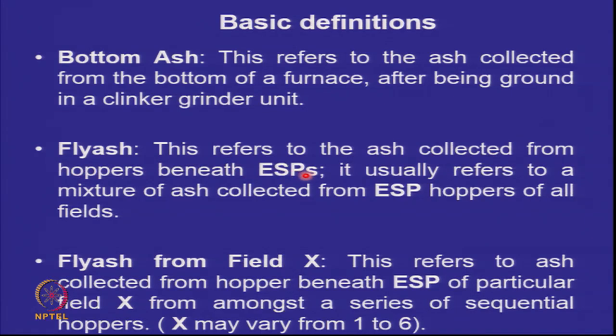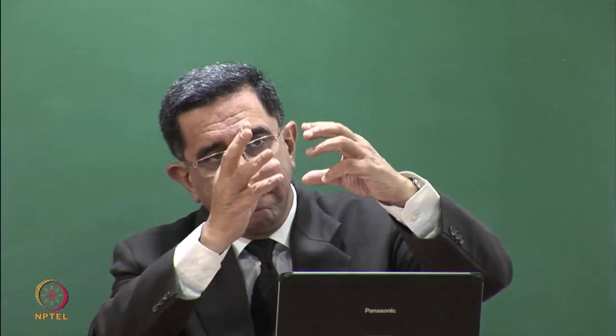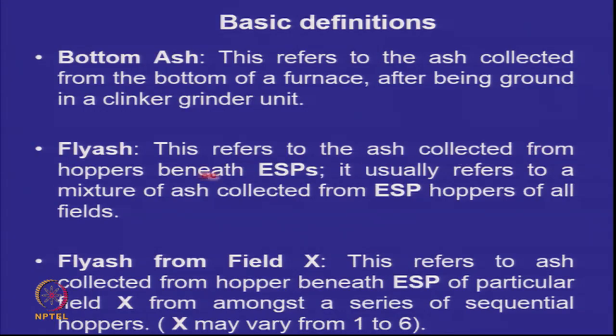Fly ash refers to the ash collected from the hoppers beneath the electrostatic precipitators (ESPs). As flue gases pass through a series of plates — referred to as fields (1 through 6) — particles settle progressively: coarser particles in field 1, finer particles in field 2, and so on, with the finest particles caught in field 6. These finest particles are small in quantity but often very useful for industrial applications such as ceramics.